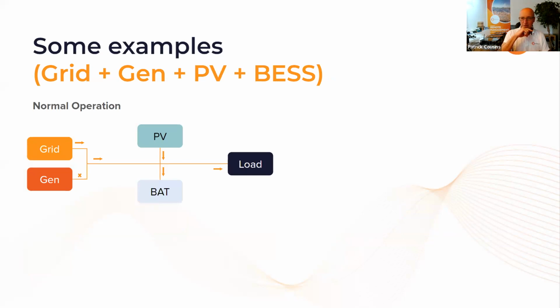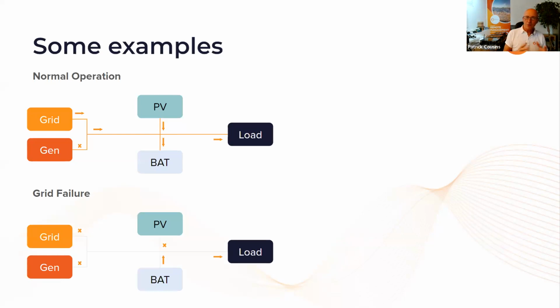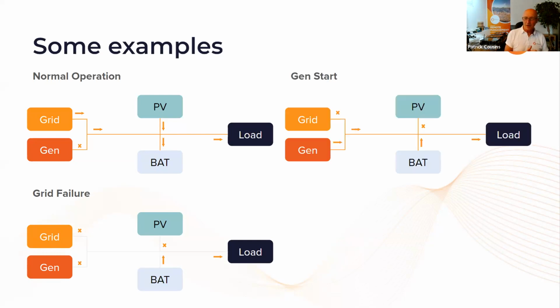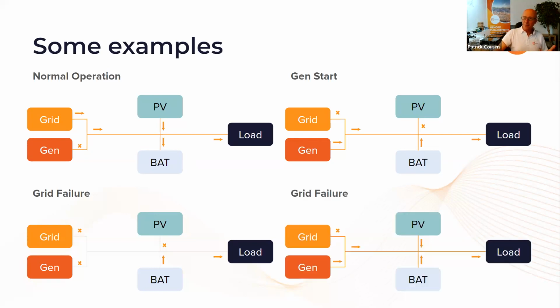Again, this will depend on the control features of the battery PV system as well. But you also get a grid failure, at which point, of course, the battery can go ahead and take over and provide the load with power, possibly without any break. What can happen, though, is that the PV will shut off because the battery system is not aligned or synchronized with the grid. And then the battery will be providing power, and then at some point the PV can come back up and it will be operating together with the battery and generator system.